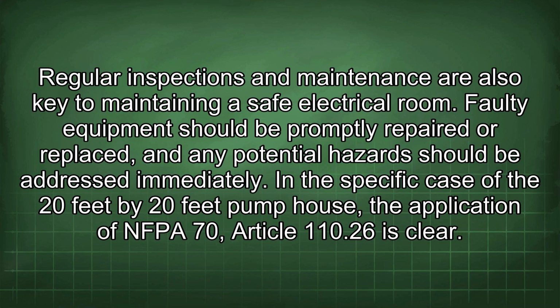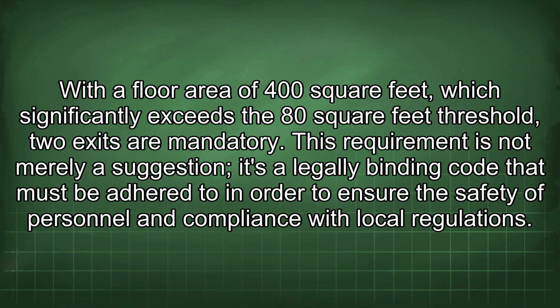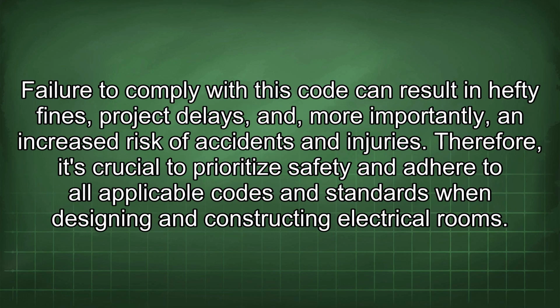In this specific case of the 20 feet by 20 feet pump house, the application of NFPA 70 Article 110.26 is clear. With a floor area of 400 square feet, which significantly exceeds the 80 square feet threshold, 2 exits are mandatory. This requirement is not merely a suggestion, it's a legally binding code that must be adhered to in order to ensure the safety of personnel and compliance with local regulations. Failure to comply with this code can result in hefty fines, project delays, and, more importantly, an increased risk of accidents and injuries. Therefore, it's crucial to prioritize safety and adhere to all applicable codes and standards when designing and constructing electrical rooms.